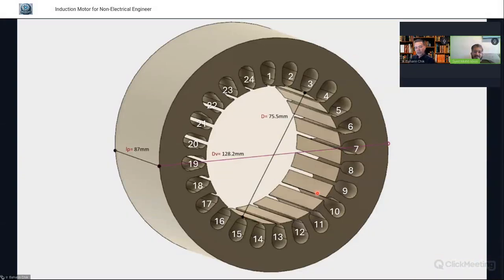No, actually, you need to check on the bearing side. You need to check whether the vibration is high or not. Then you check also on the displacement of the air gap. Between the stator and rotor, there's an air gap in between. If you take, for example, this year a certain air gap, and maybe next month you see that the air gap is not uniform, so this side has more gap than the other side, then you know that there is something wrong with the bearings.